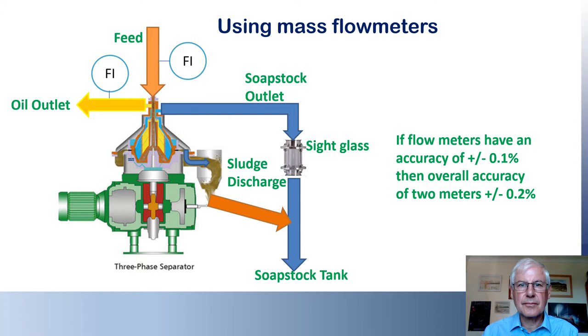You have to totalize the flow for over an hour or more to get a good idea of the total loss, including the sludge discharge. If the flow meters have an accuracy of plus or minus 0.1%, which is fairly typical, then the overall measurement could be out by up to 0.2% — okay for daily monitoring, but we need to do better than this if we want to balance flows to within one part in a thousand.